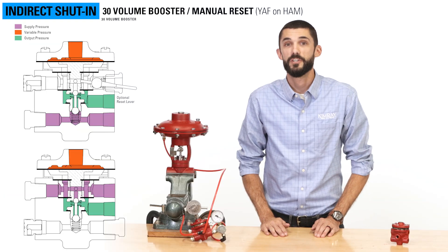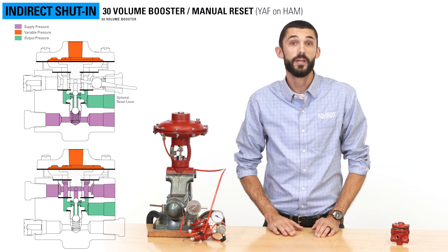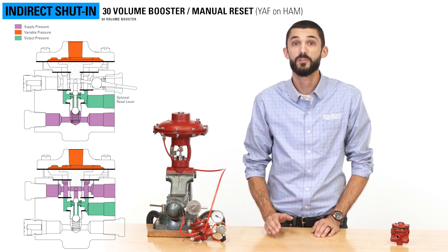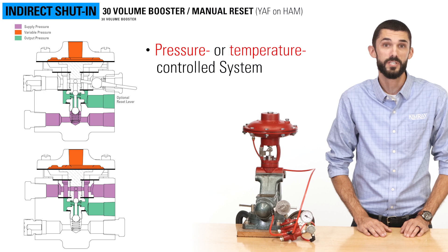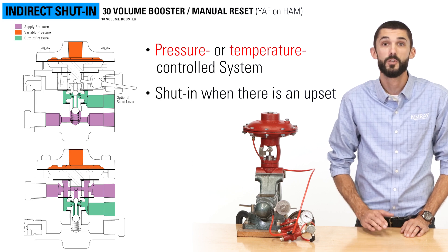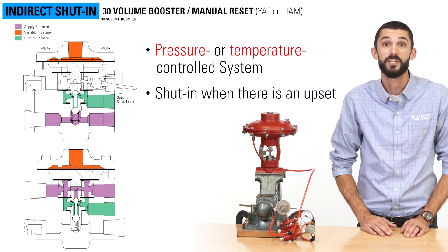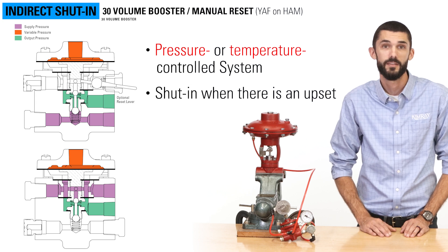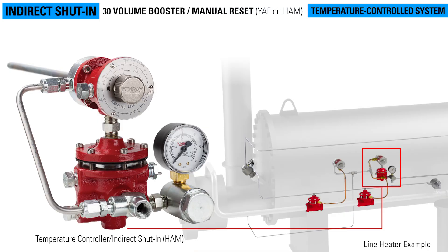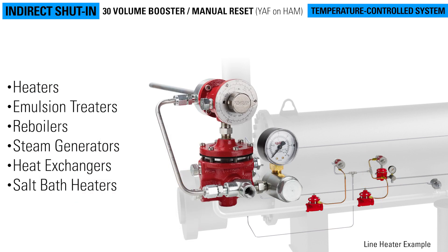A second application for a pneumatic relay is for indirect shut-in. Indirect shut-in refers to either a pressure or temperature controlled system that is shut in when there is an upset, so that the process does not continue until manually reset. In a temperature controlled system, the indirect shut-in uses a relay to shut down a process to prevent damage to the equipment in the event that the temperature goes over its set point. These can be used in heaters, emulsion treaters, reboilers, steam generators, heat exchangers, and salt bath heaters.